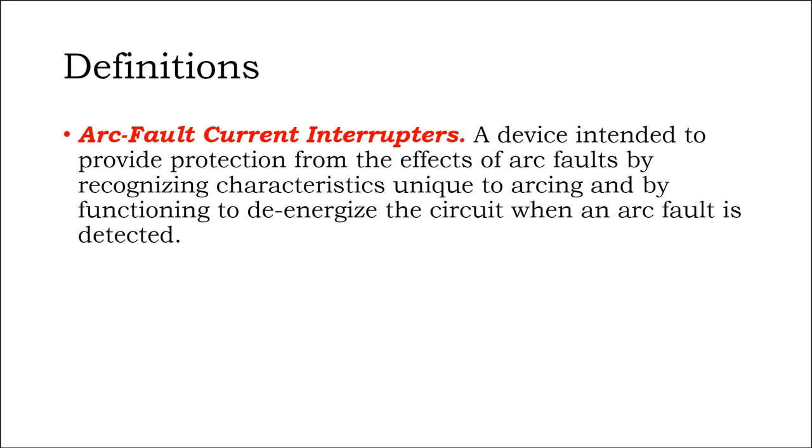Now, the solar industry has been required to put arc fault detection capabilities into their inverters. So back in the day, you fire up a system and it works perfectly, and everyone goes home happy. With an arc fault detecting inverter, the inverter could say, one of those connections out at the array isn't made up correctly, it's a little loose and causing a little bit of arc faulting in the connector, so you need to go fix that before I turn on.